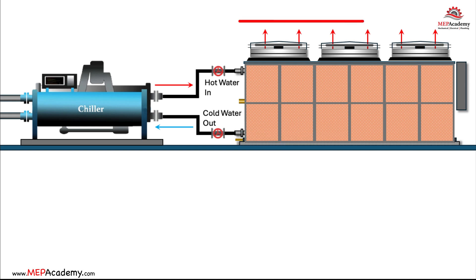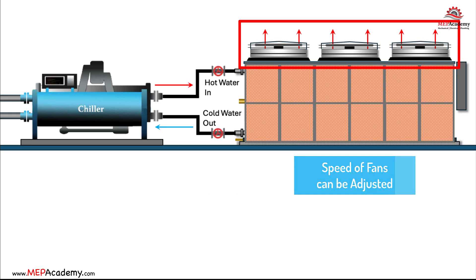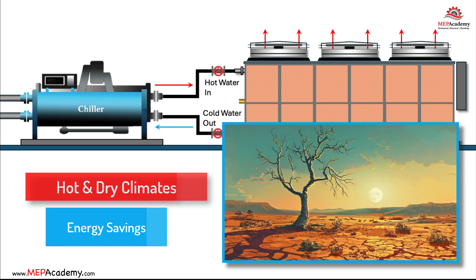The fans inside the adiabatic fluid cooler draw air through the wetted medium and across the heat exchanger to facilitate the cooling process. The speed of the fans can be adjusted to control the cooling capacity of the unit. By combining evaporative cooling with a traditional heat exchanger, adiabatic fluid coolers can achieve significant energy savings compared to conventional air-cooled heat exchangers, especially in hot and dry climates where evaporative cooling is particularly effective.